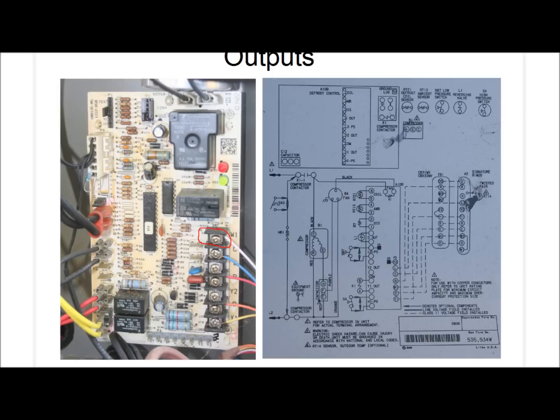So this W1 terminal sends 24 volts back out to turn on the electric strip heat. Now we'll talk more about that in another lesson when we get into the heating and defrost mode, but that is an output there. And let's talk about these terminals over here on the left. These are all output terminals, and they are 24 volts out. And this is what is really used to control what's going on with the condensing unit.